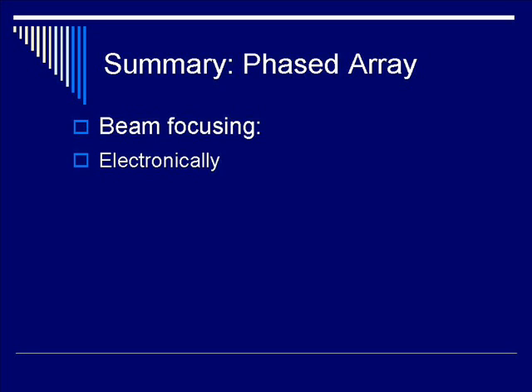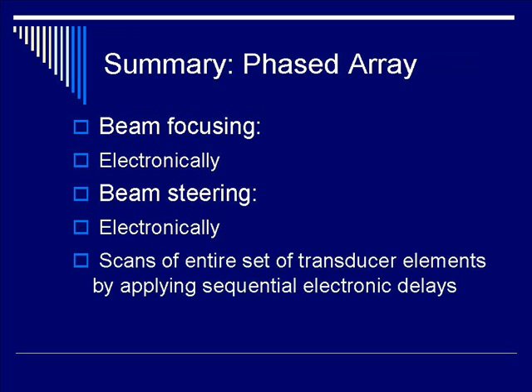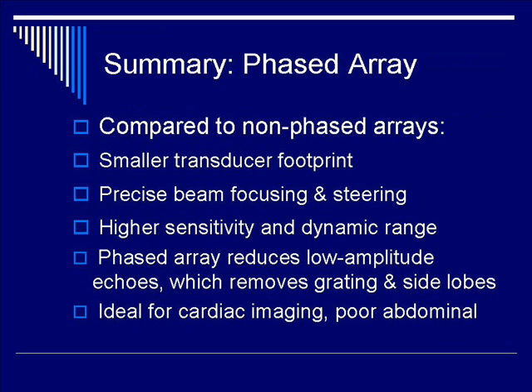In summary, for phased arrays, beam focusing and beam steering are both done electronically. Unlike linear and curvilinear arrays, phased arrays scan the entire set of transducer elements by applying sequential electronic delays. Compared to non-phased arrays, phased arrays have the advantage of a smaller transducer footprint, giving precise beam focusing and steering, as well as higher sensitivity and larger dynamic range. Phased arrays reduce the low-amplitude echoes inherent in ultrasound reflections, which removes grating side lobes from the ultrasound signals. Thus, it is ideal for cardiac imaging, yet is poor for abdominal imaging.